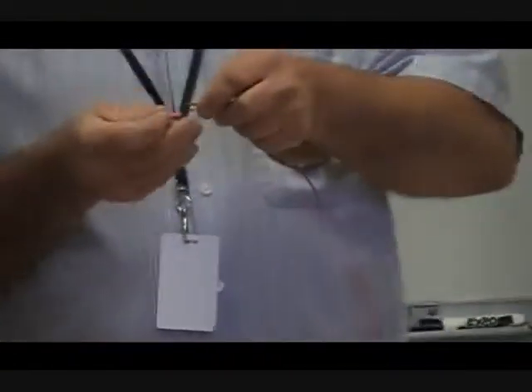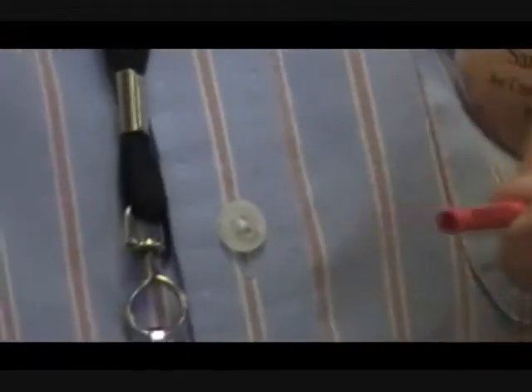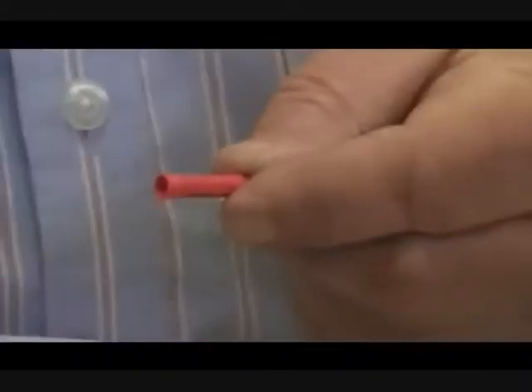What I want to do is show you some of the terminals that we do use, some of the connectors. And this is a crimp type connector. You notice that I cut the wire with a cutter and stripped it with a stripper. This particular tool right here, I did not use a box cutter, a razor, a pocket knife. The reason being, when you do, you're going to touch that wire. I don't care how good you are, you're going to touch that wire and make a place for it to break. A little bit of vibration is going to break. Another thing is you want to use the proper tool to crimp that.